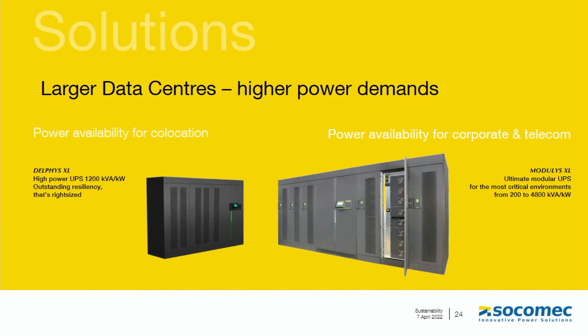Yeah, thanks, Colin. And I say, larger data centers, so the drive for larger UPS blocks, we're typically looking at 1 meg, 1.2 meg monolithic blocks now, but also looking at the larger modular UPS, such that you can add or remove capacity as and when and as the load changes.